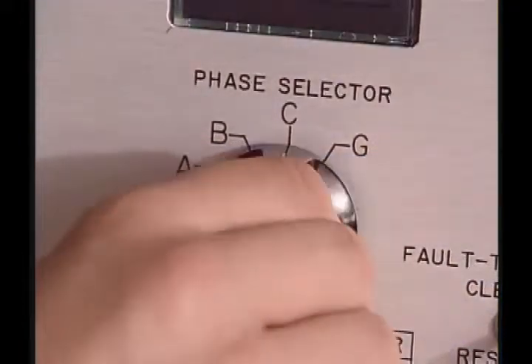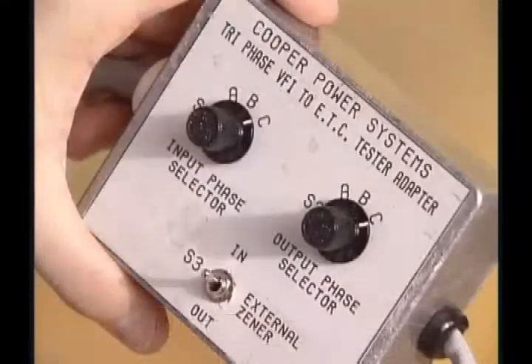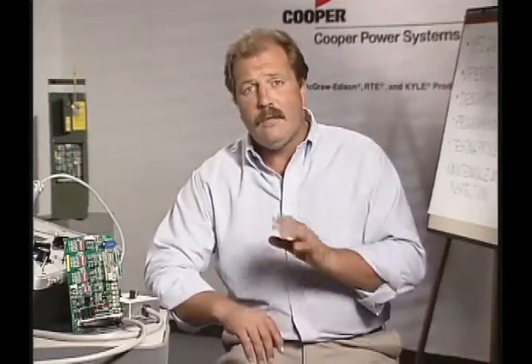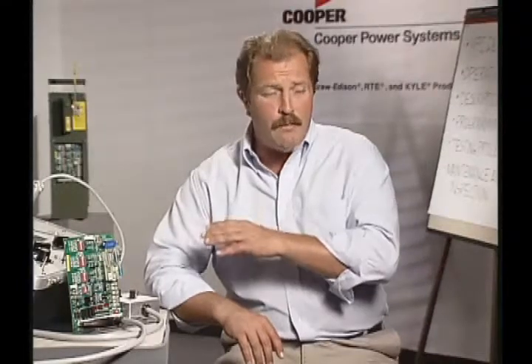Set the ETC phase selector switch and adapter cable input and output phase selector switches to the phase B or C position. If the measured minimum trip current falls outside the plus or minus 20% range, or if the control fails to trip the interrupter simulator, the control circuit board must be replaced.